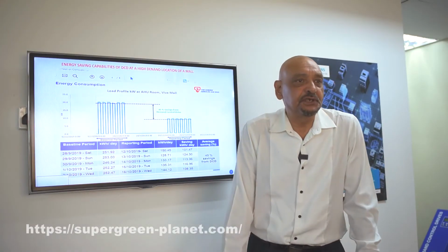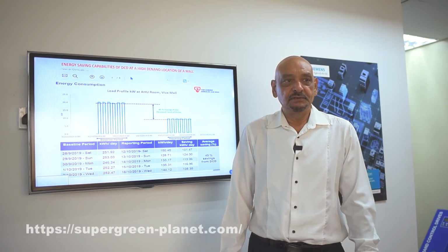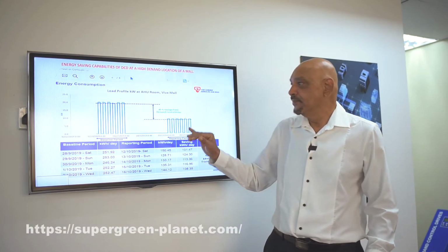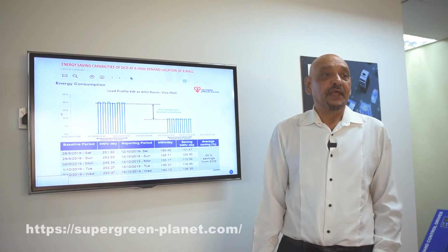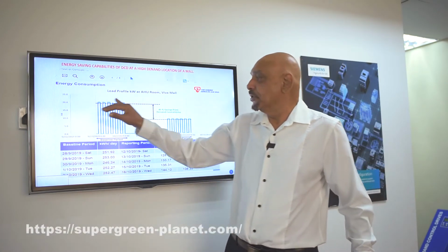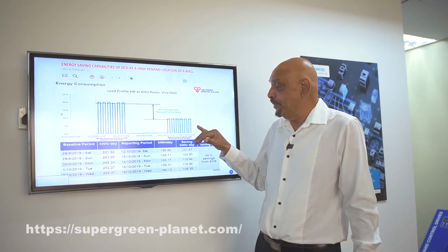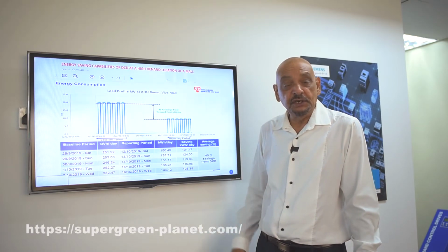After that 2 weeks test period, the data loggers were taken down, the temperature meters were taken down, and a report was generated. And if you see the result here, this is the baseline. That is the electricity consumption, about 20 kilowatt an hour. And after DCD, what you get is a 45% reduction in your kilowatt hour consumption. At the slide before that, you have seen that the temperature within the environment was as good or probably slightly better than what it was before the DCD, and the humidity was very, very consistent.